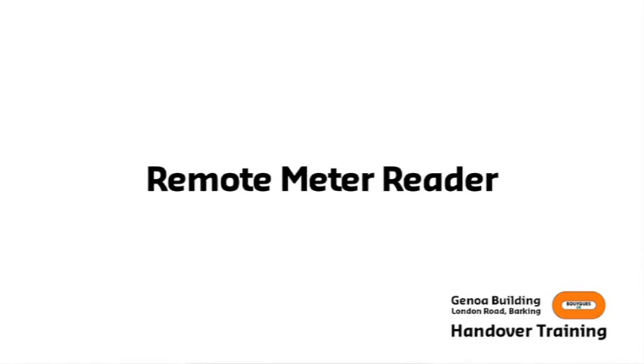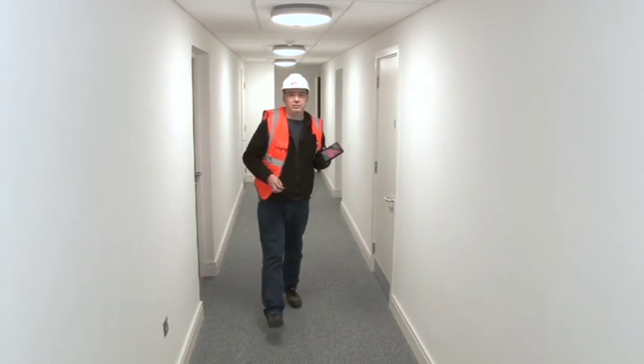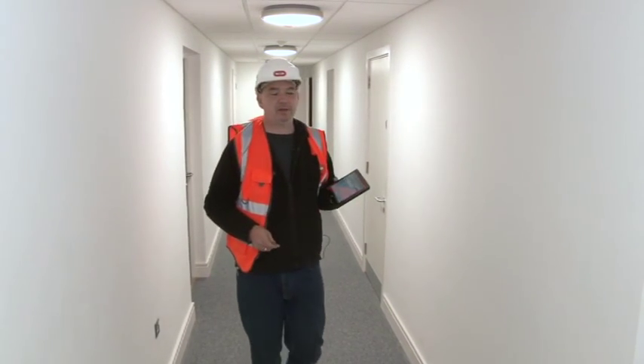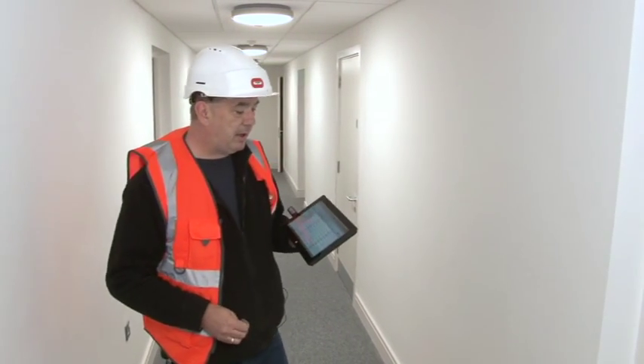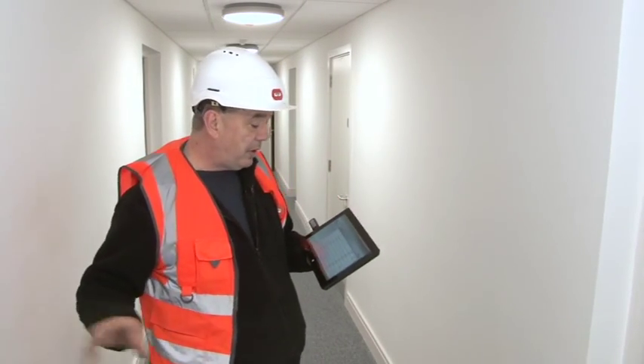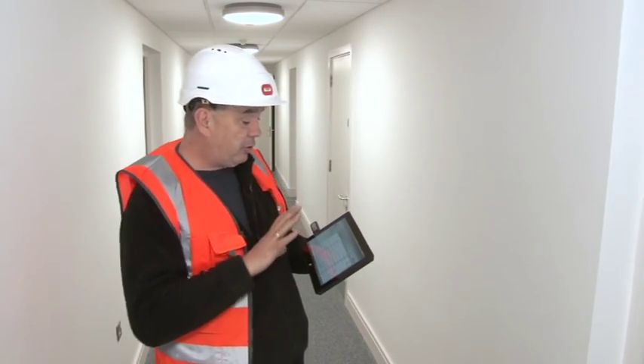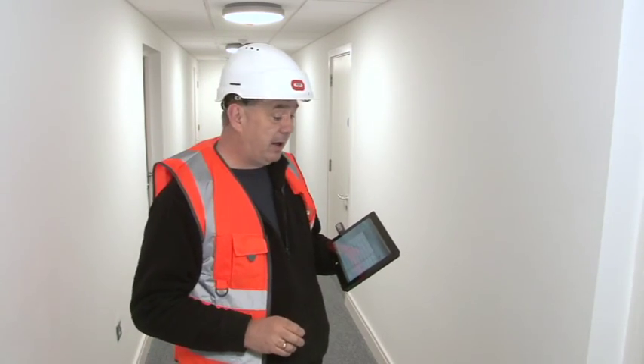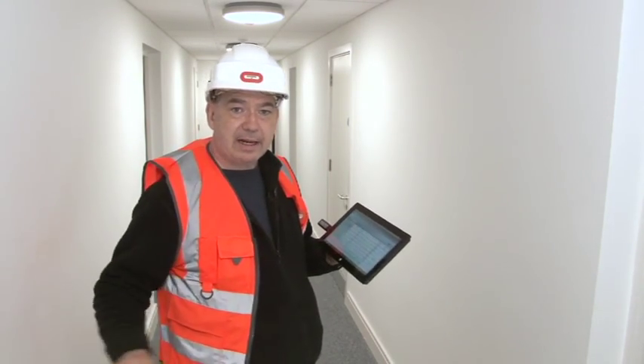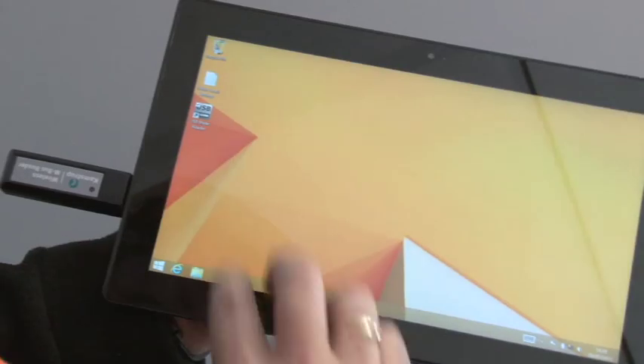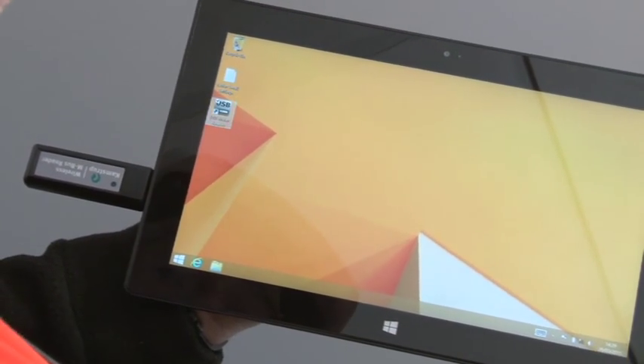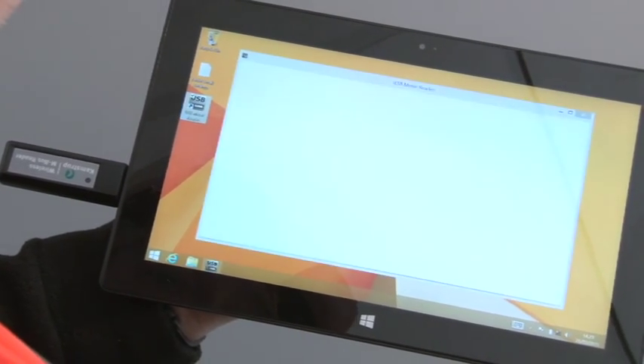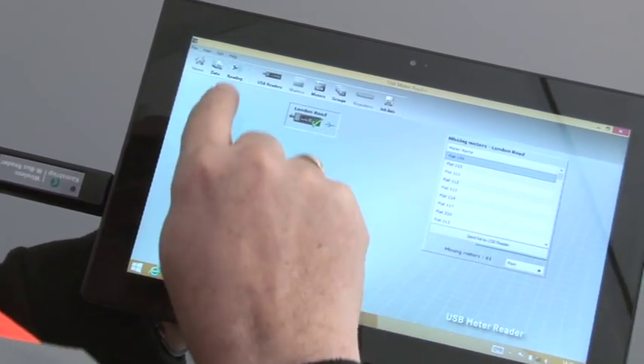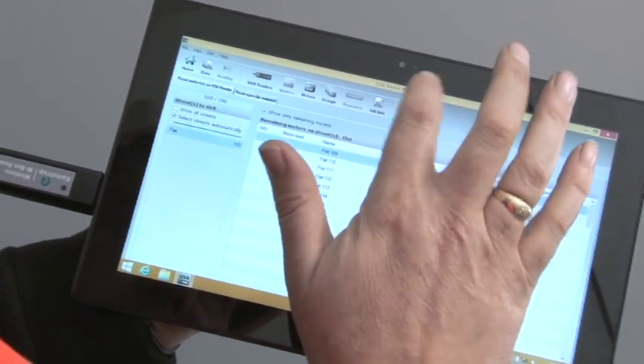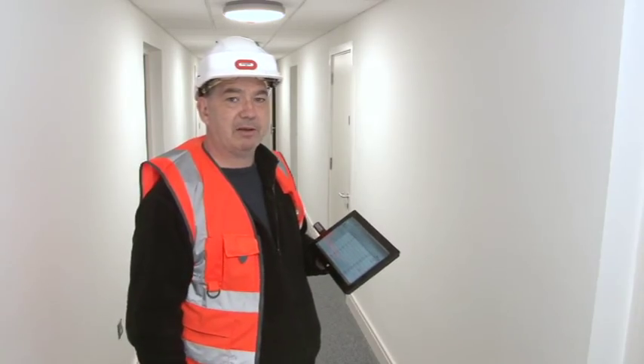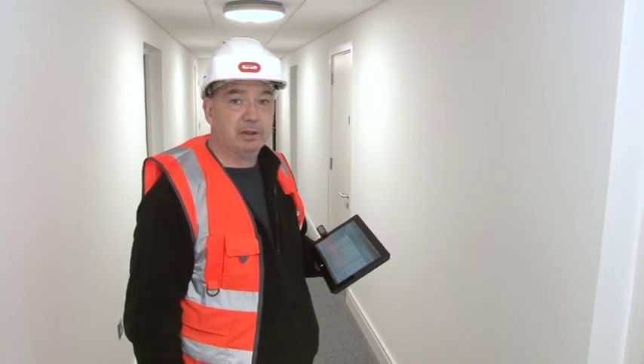Right, what we've actually got here is a remote meter reader so that we can record what the tenant's usage is on their heating and the hot water, and it saves someone coming round, knocking on the door, asking you what your meter reading is. It can all be done remotely throughout the building, and then all the information is gathered and sent down to the people who release the bills. It works on a radio frequency, and each of the meters has a little radio module in there so that it grabs all of the information, so that it's accurately billed for the amount of energy that you use within your apartment.